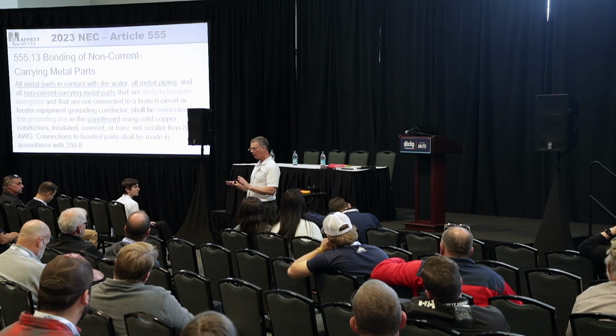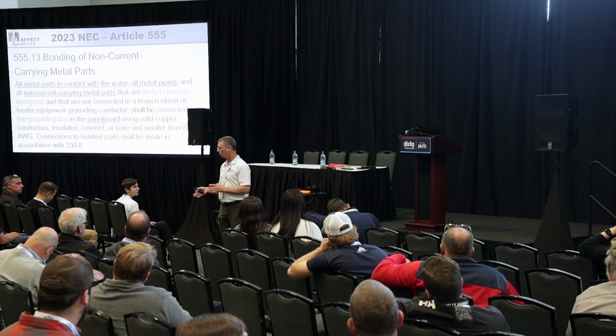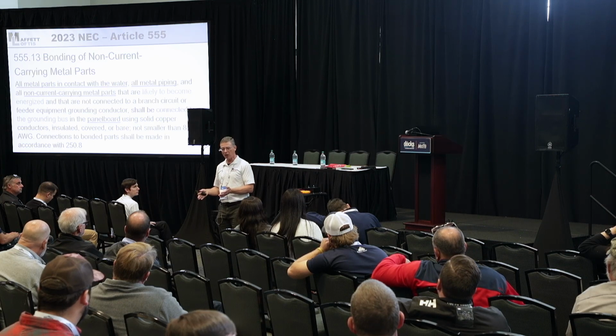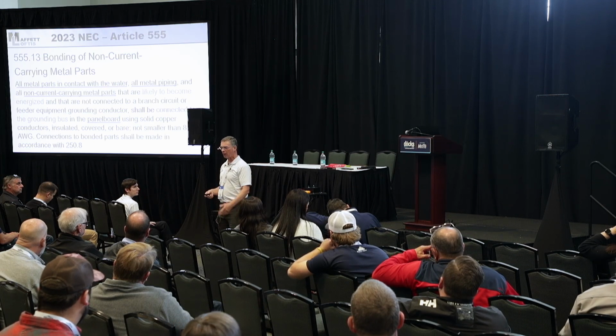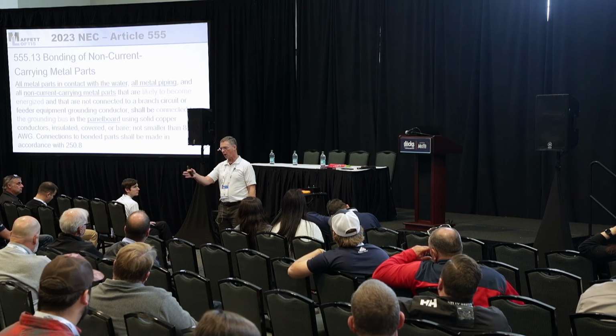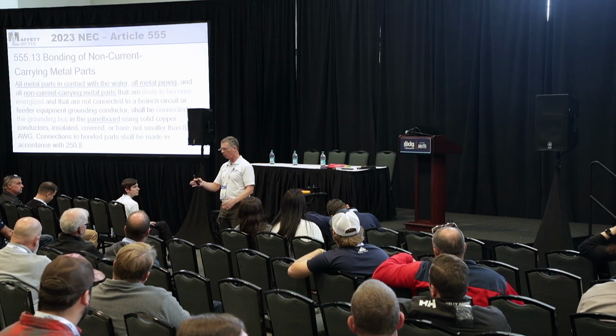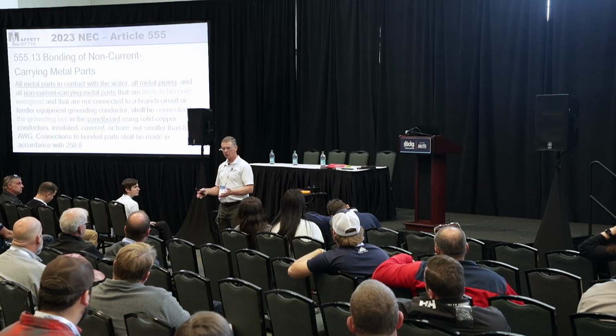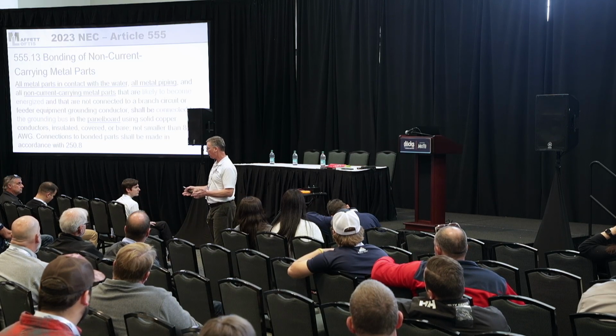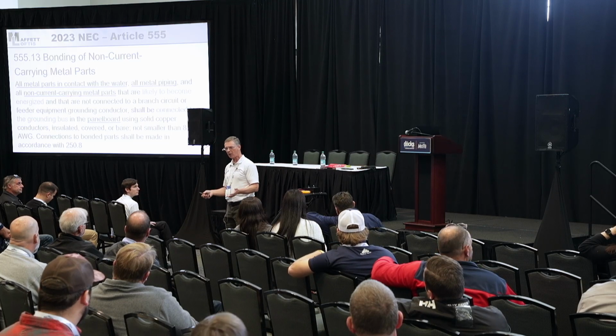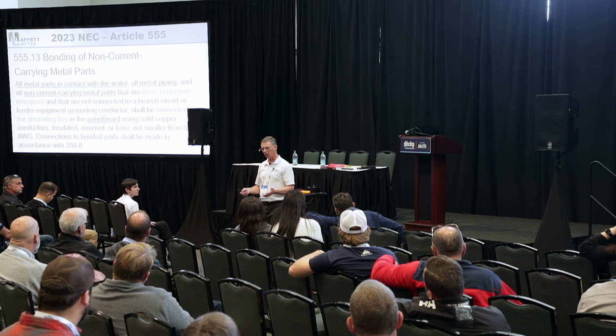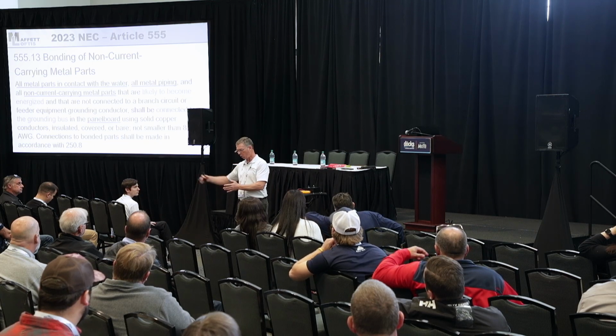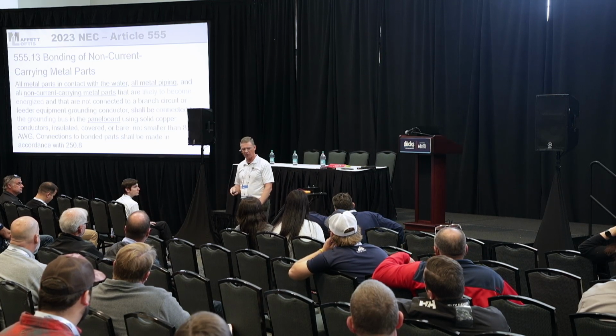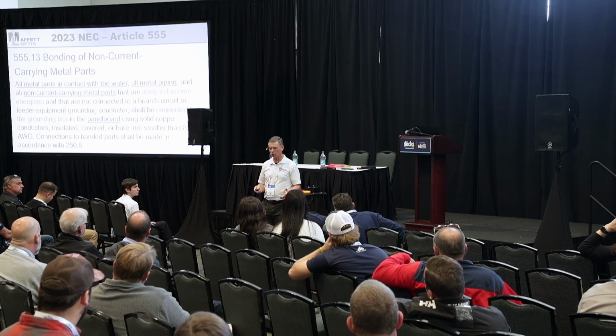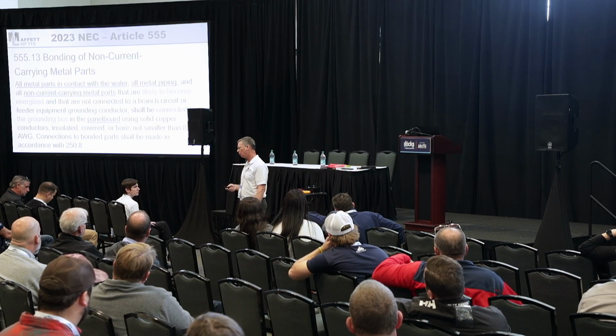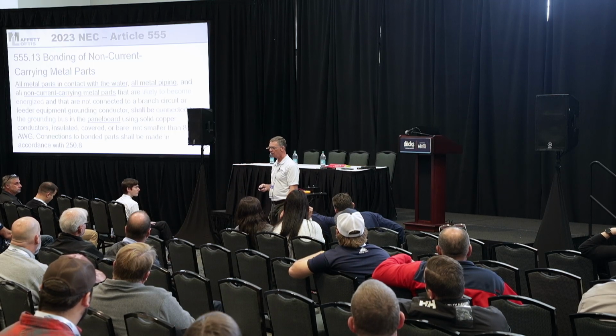The intent was that any piece of metal that's likely to be energized shall be bonded. And that's what it needs to be, because if you have, say, a galvanized truss frame on a freshwater lake and you're running electrical conduits through it, at some point, through storm damage or just wear and tear, that dock's structure could be energized by that conduit and that electrical wire. That galvanized truss system needs to be bonded because it's likely to be energized. But a spud pole that is way away, or a spud pole at the end of a finger with no electrical conduits around it at all, is not likely to be energized. But some inspectors are saying it has to be because it's in the 2023 code like that.